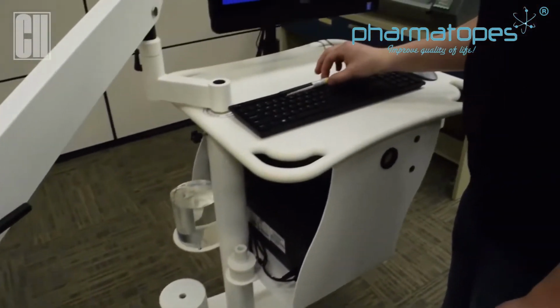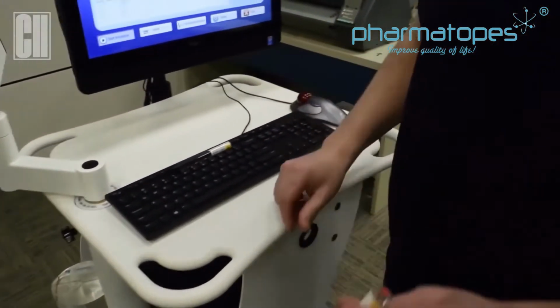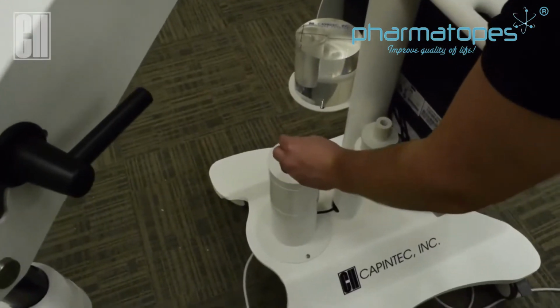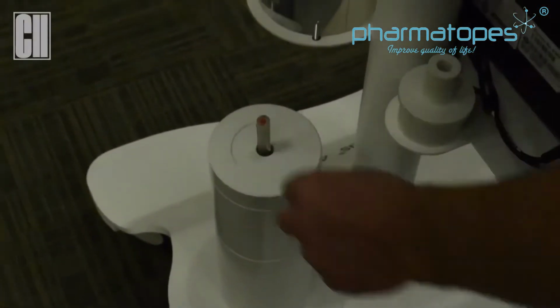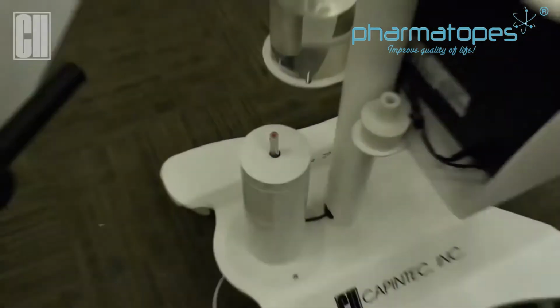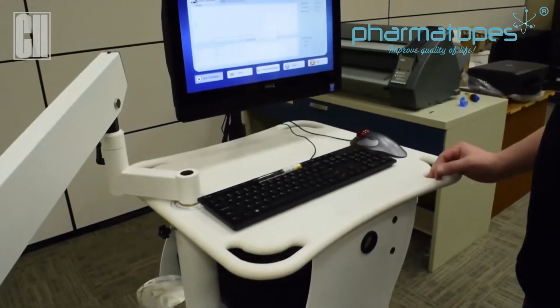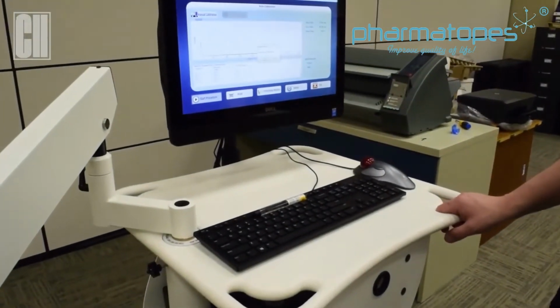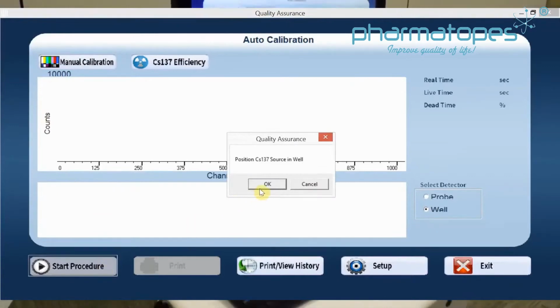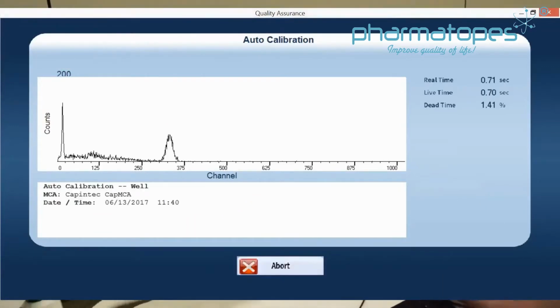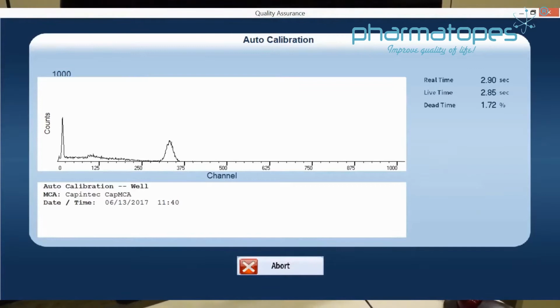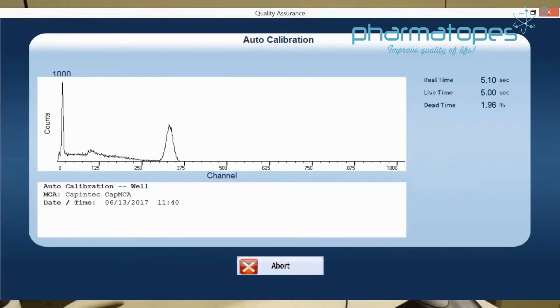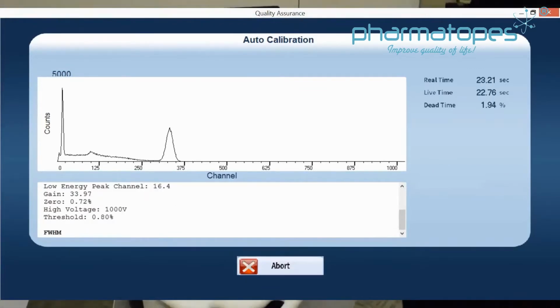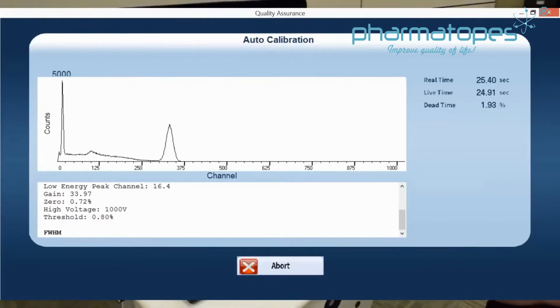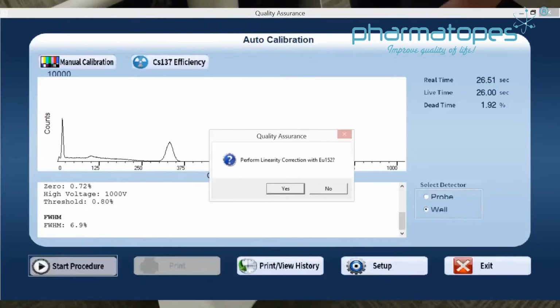Now we can get the cesium source and position it into the well. Again, we want the black tip down, place it into the well. Once the source is in place, we can click OK. And now we're going to do the calibration on the well. Once the calibration for cesium is completed, we're going to do linearity on the well detector now. Okay, so now that the calibration is complete, we're going to do linearity with europium.